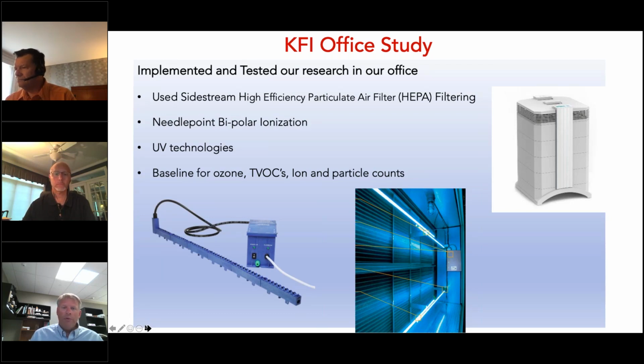And so what we came up with, at the end of the testing, is we had about a 65% reduction in particle counts in the COVID particle size range, which for side streaming about 20% of our air, we thought was very good results. And as Mark talked about, it's not just one thing. We think it was a combination of the things we did to get that improvement. And it shows on that chart that Mark showed at the end. What we tried to do is reduce the risk for every occupant in our office, the risk of them coming in the office. Next slide.